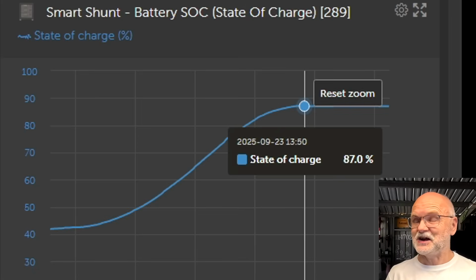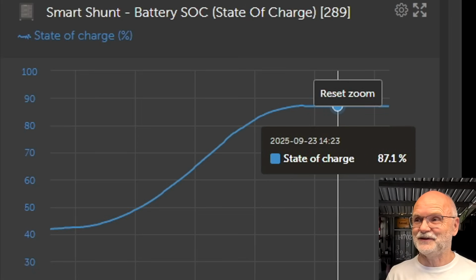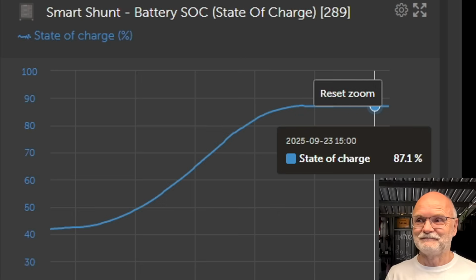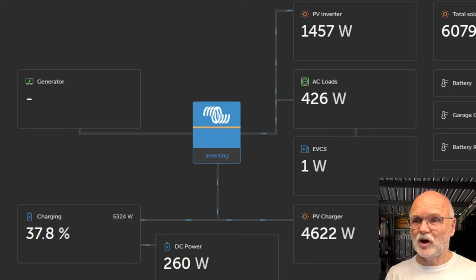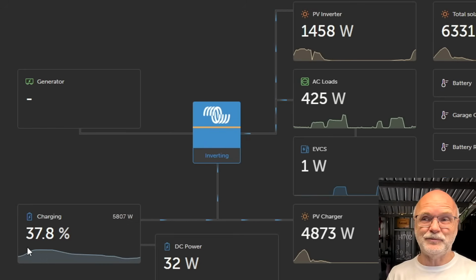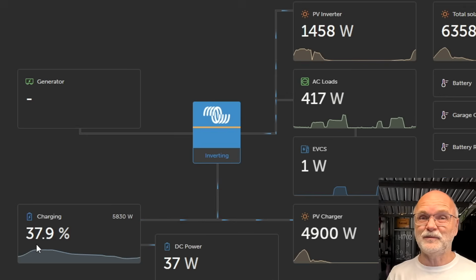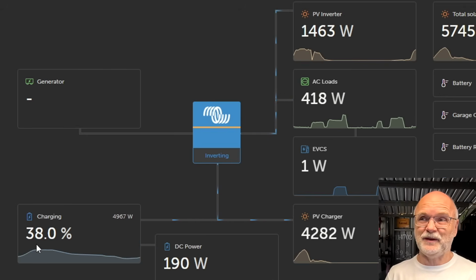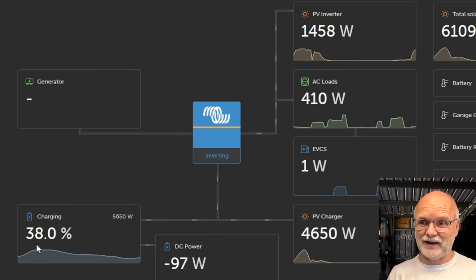If you turn on more load than you have solar, energy comes from the battery again. If the load disappears, solar will only recharge your battery to 3.35 volts. So the state of charge on the Smart Shunt stays at 87% — it didn't move because we haven't met the three criteria to reset to 100%. So it looks like this Smart Shunt is actually 13% off: the battery was full, but it shows only 87%. Going back to today's dashboard and adding 13% on top of the 37% here, we're already at 50%. So keep this in mind — we need to recharge the battery by 50% now to get back to 100%.